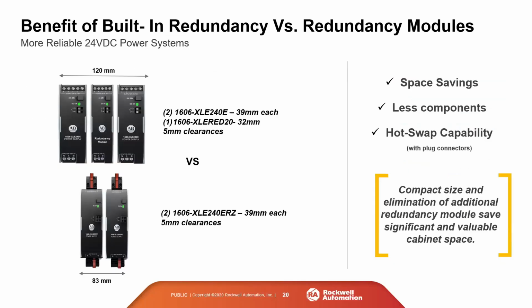So building a redundant system using built-in redundancy has numerous advantages. Obviously, you can just look at the picture and see that there are three components for our system with the redundancy module, and only two. So right off the bat, you're saving the entire price of one component. But you're also saving around 40 millimeters of space. On one panel, maybe 40 millimeters of space is not that big a deal. But if you're doing hundreds of panels, that's significant space savings and significant component savings as well. So just something to keep in mind.